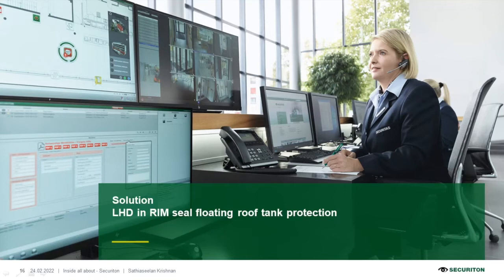Basically, to answer this question, they're quite similar, but the other precautions you need to take, I'll show you in the solution, whereby extra cables are needed, and a special place to cap these ADWs is needed because it's moving and it's also floating in terms of the Rim Seal application. In terms of the external, it is stagnant. Therefore, a permanent place to put the ADW is enough, and no extra cables are needed. Otherwise, how you run the cable and detection would be the same.